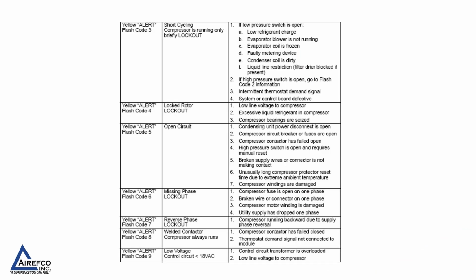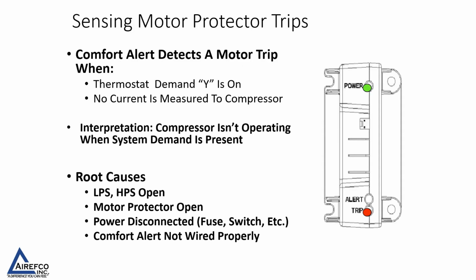This table, also available in the user manual, shows you the flash codes that the yellow alert LED will use to tell you what the system is locked out on. If the red LED is on solid, as we've said, this means that there is a demand on Y, but there is no measured current to the compressor. So the compressor isn't operating when the system demand is present. Some root causes could be the low pressure or high pressure switch is open, a motor protector is open, fuses or switches could be open, or the Comfort Alert may not be wired correctly.